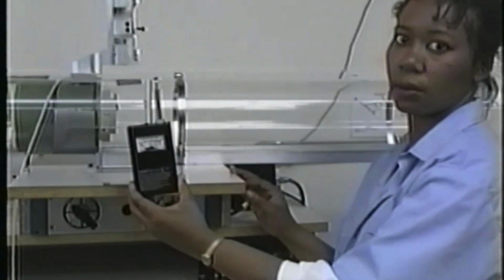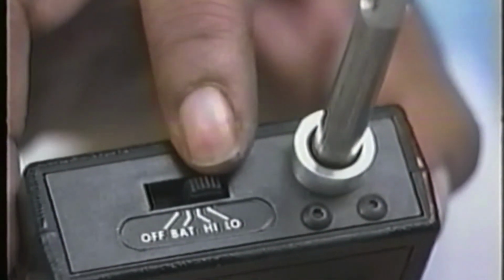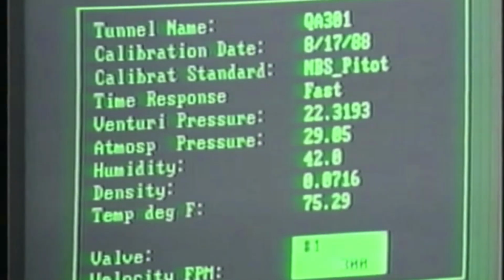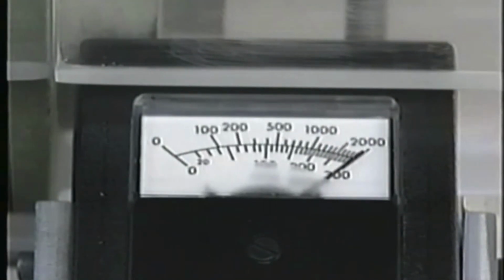To make the low span adjustment, set the instrument in the wind tunnel with the probe positioned so that the airflow is in the direction of the arrow on the probe. Turn the unit to the low position. Set the wind tunnel to 300 feet per minute and turn the low span adjustment screw labeled L span on the left-hand side of the instrument until the meter needle lines up with the 300 feet per minute division.